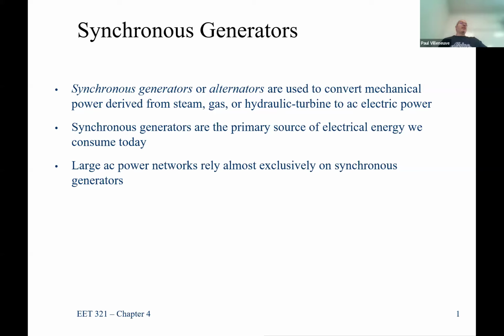What we'll start to learn as we get through the material on synchronous machines is that they're really good for providing lots and lots of fault current. So we spend most of our time on synchronous generators, because large AC power networks rely almost exclusively on synchronous generators. It's not quite that bad, but it's still the preponderance of your AC power that you get from your wall socket that's going to be from a synchronous generator.